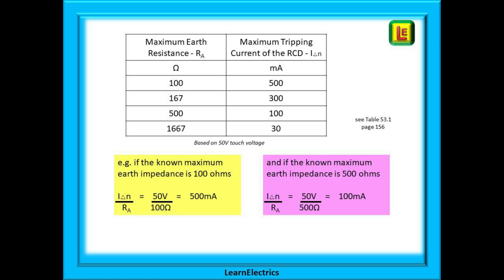If we know the earth fault impedance in ohms we can quickly determine the tripping current required. We use a touch voltage of 50 volts, since below 50 volts a normal healthy adult is unlikely to receive a fatal electric shock. A properly selected RCD should trip before the voltage on exposed metalwork rises above 50 volts during a fault. 50 volts divided by 100 ohms will give a tripping value of 500 milliamps, and 50 volts divided by a soil impedance of 500 ohms will give a tripping value of 100 milliamps. That makes selection easy.